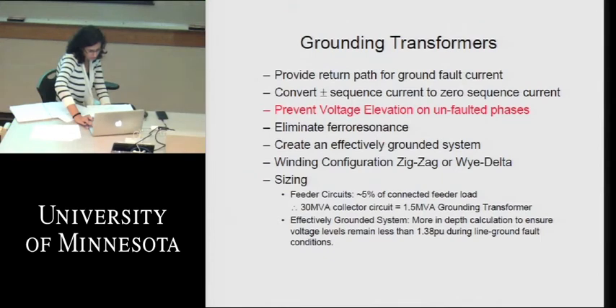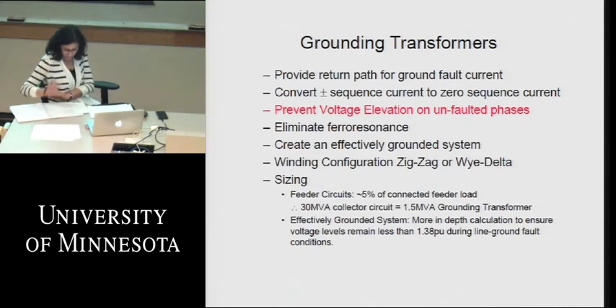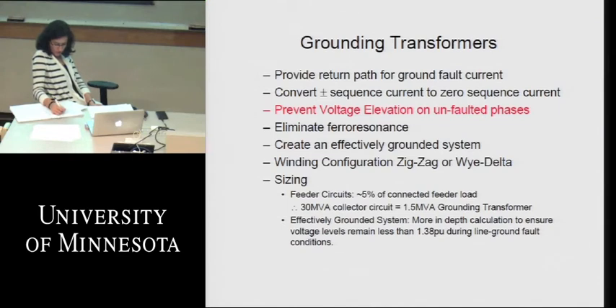Next slide. They provide a good return path for the ground fault current, convert positive and negative sequence current to zero sequence type currents that would be detected by the ground fault relay, prevent these overvoltages on the unfaulted other phases, help eliminate ferroresonance, or the resonance of the transformers when they get in very saturated conditions, and create an effectively grounded system. The grounding transformer can be connected in different configurations also here.